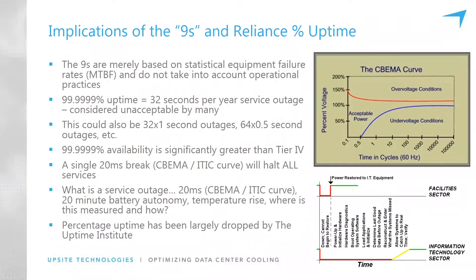Anything more than a 20-millisecond outage is going to take out pretty much the entire IT load — certainly a 25-millisecond outage. And yet in the industry we continue to talk about percentage uptimes in terms of the nines without really understanding what it means. This also explains why the Uptime Institute dropped percentage uptime, and that was some time ago.